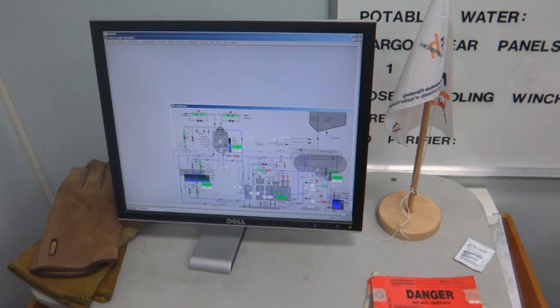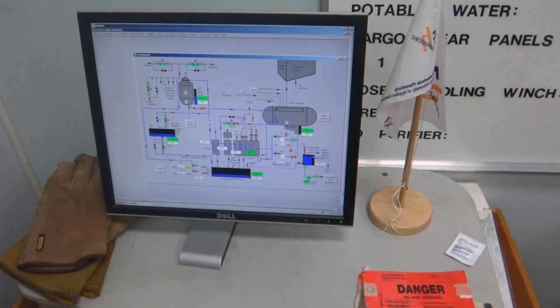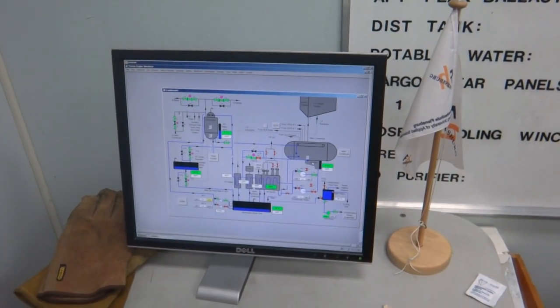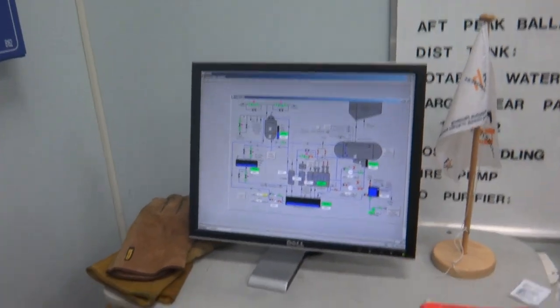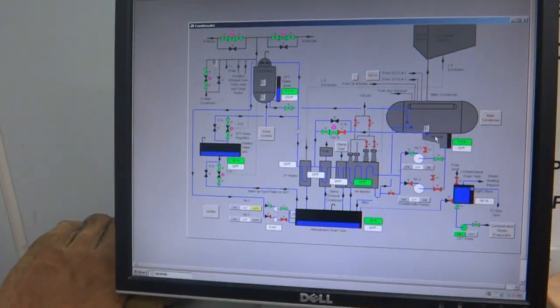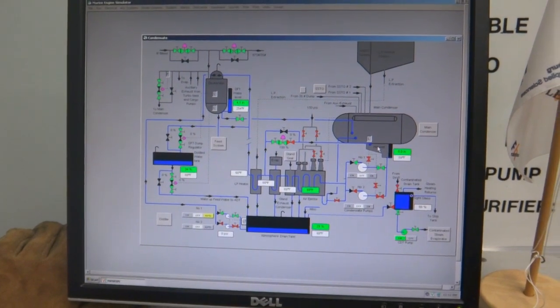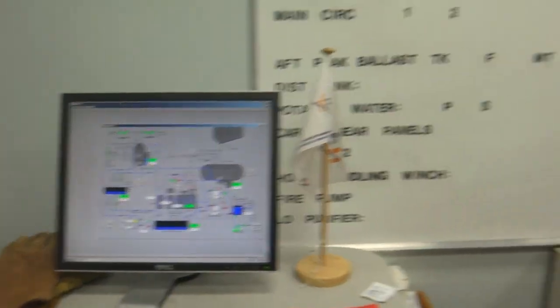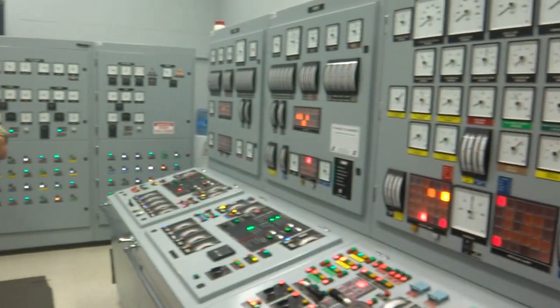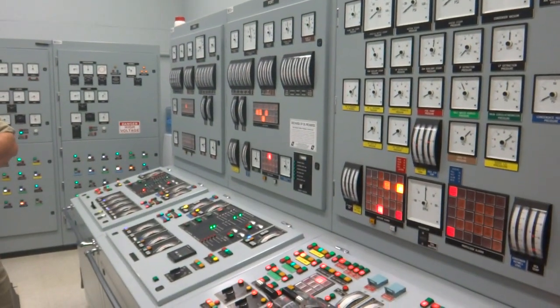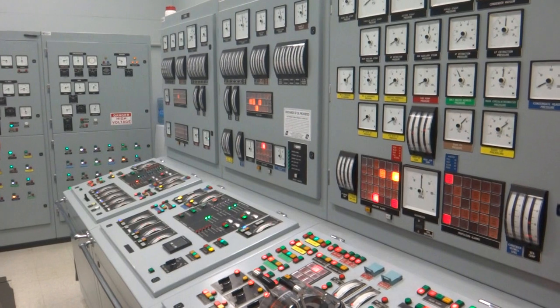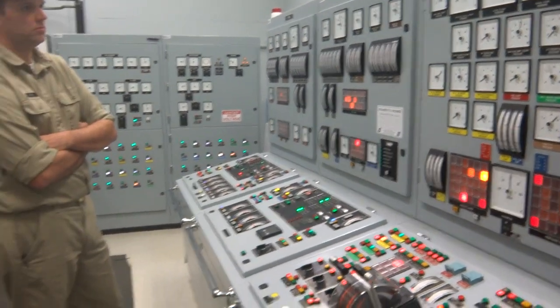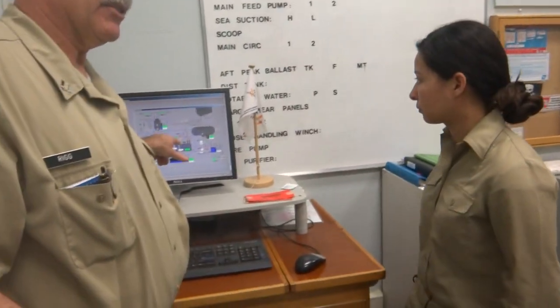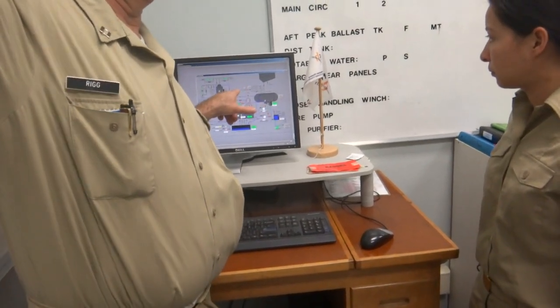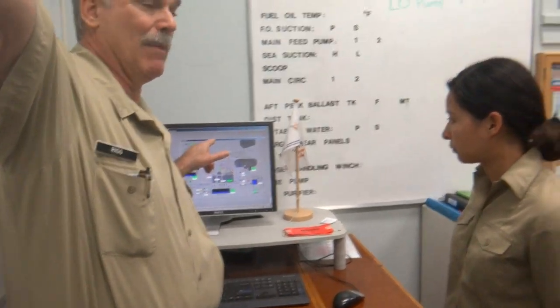So we go to condensate, and now we can open this valve here, and the hot well will come up. So we got that. While we're doing this, it's going to take some time. Let's cut in on the 150 pound. We're good. Let's shut the bypass, open up the regulator for the 150 pound upstairs in the fiddley. We've got the recirc. Let's open up the recirc and the bypass on the recirc for the condensate recirc, which is over there by the number 1 burner.